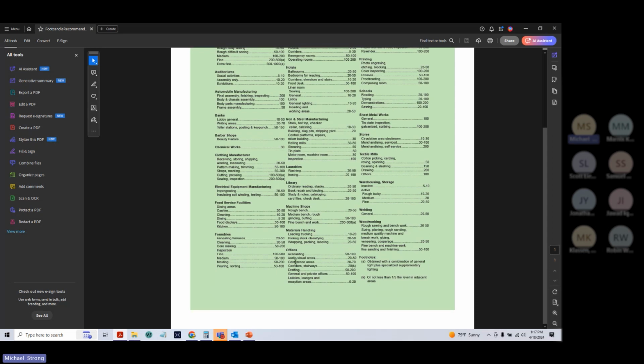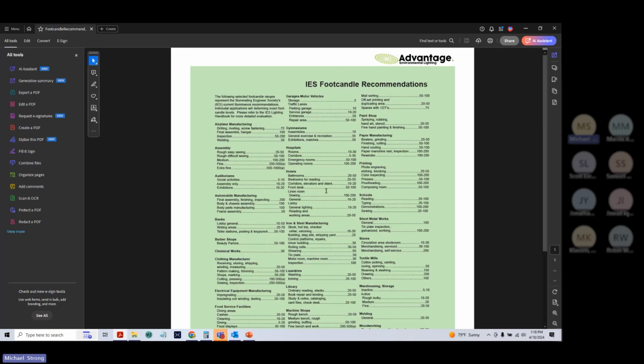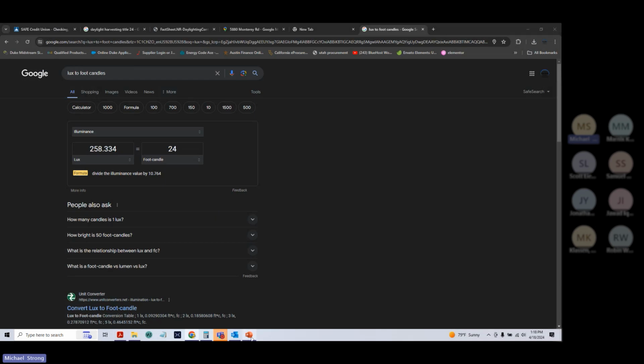So for example, in our case here, we have lobbies and reception areas, and they give you a nice range of where those foot candle measurements should be. And that makes it simpler for us to roll out daylight harvesting methods. So, obviously, if you have built a lighting package to be 30-foot candle, that's going to be the maximum output. So even with daylight, you might get an extra 20-foot candle, but we would never be able to get higher than what the daylight and the natural light would produce together. So keep that in mind when looking at this, but we will hand this out if you don't already have it. If you need that, don't hesitate to ask.